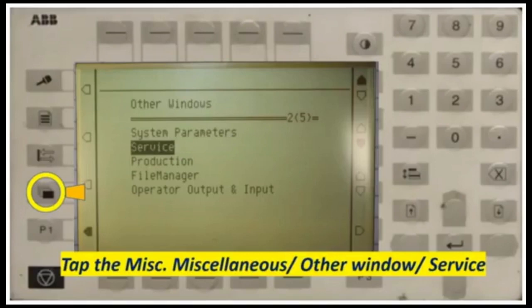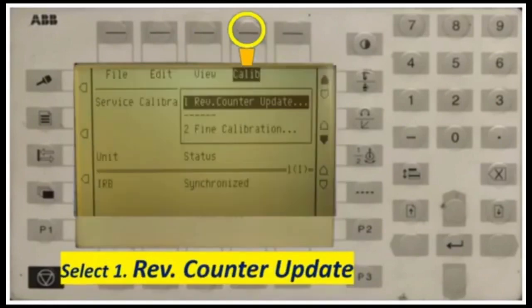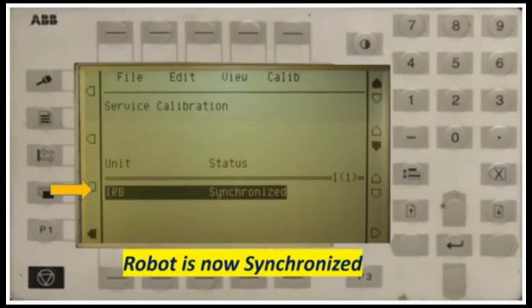Tap the Miscellaneous window, then select Service. After that, click View and select number three, Calibration. After that, select number one, Revolution Counter Update. If you want to do fine calibration, choose number two. To update, include axes and press OK to confirm. Your robot is now synchronized.